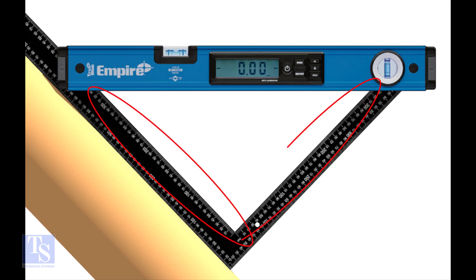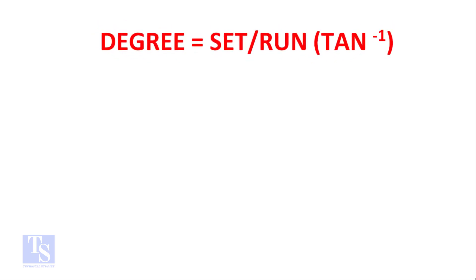Now we have the set and the run of the pipe. Let us apply the tan theta rule. Degree equals set divided by run, tan inverse.